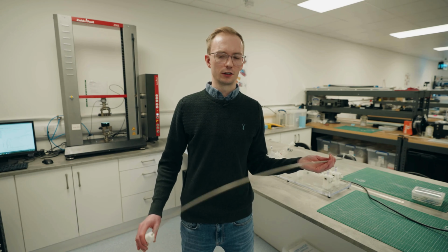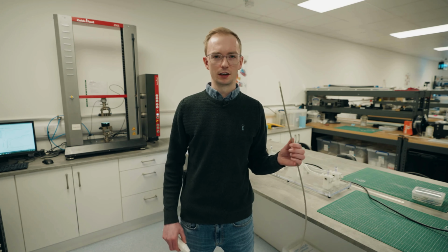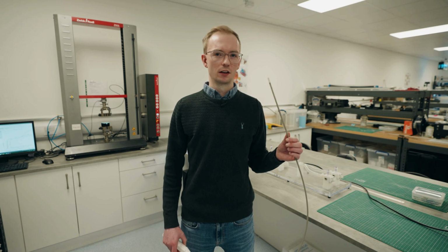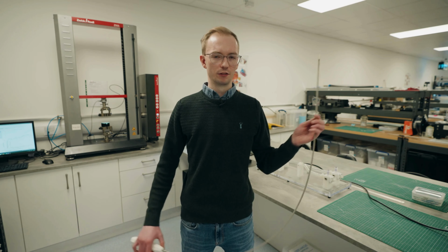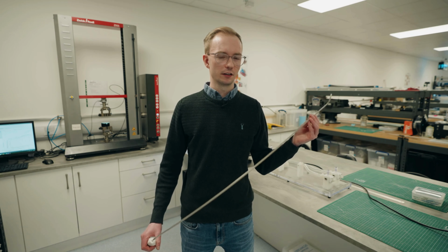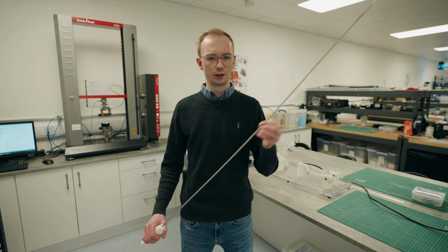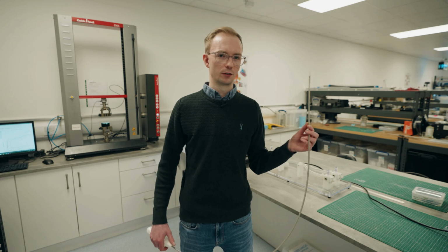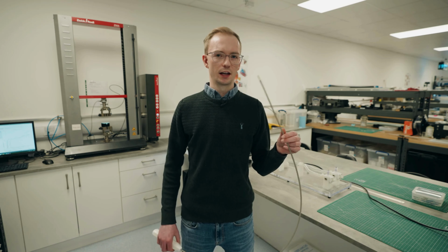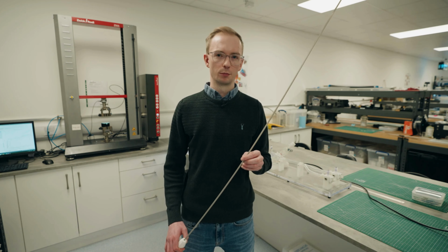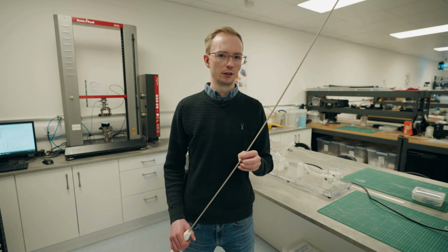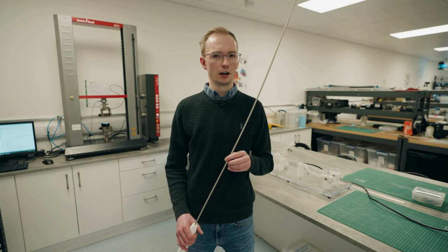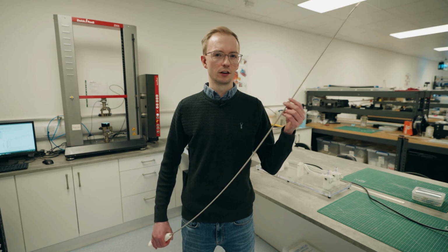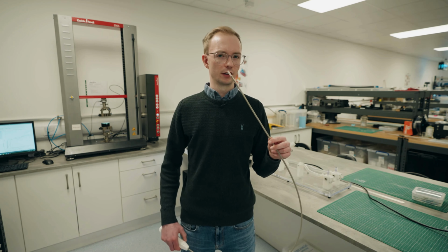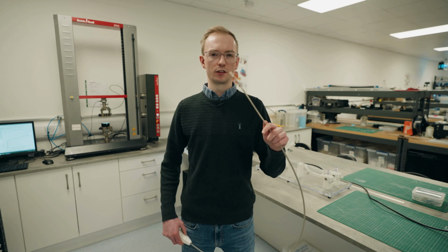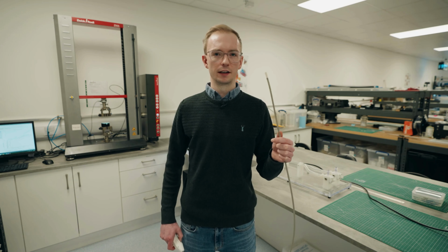Some of the challenges with steerable catheters is we often look for a combination of mechanical properties. So how we overcome that is using various jacket durometers in one catheter length. So like I said, we can start with a stiffer durometer and move up to a more flexible durometer at the distal end where it's needed. And we can also do some changes in the braid, so we can use different braid densities. So we can use a higher PPI in the proximal end where we want it stiffer, and then we could use a lower PPI or density on the distal end where we want more of that flexibility and trackability on the tip of the catheter.